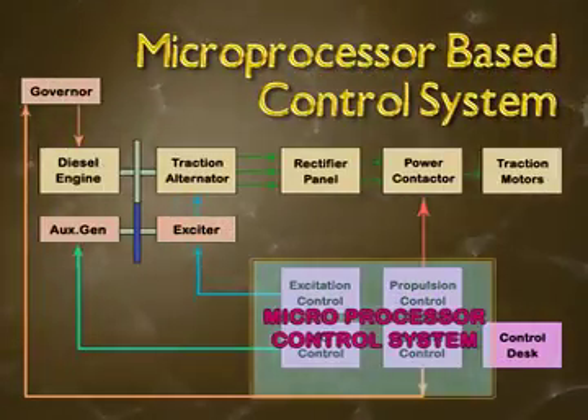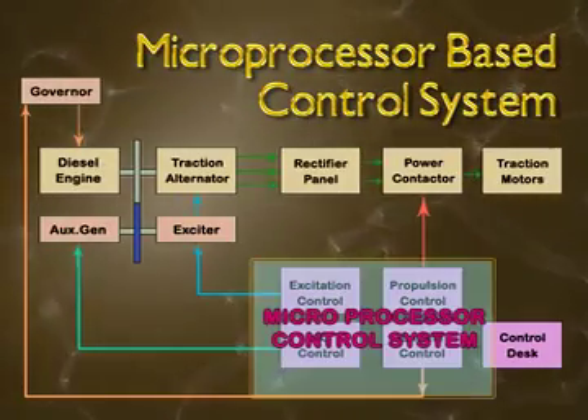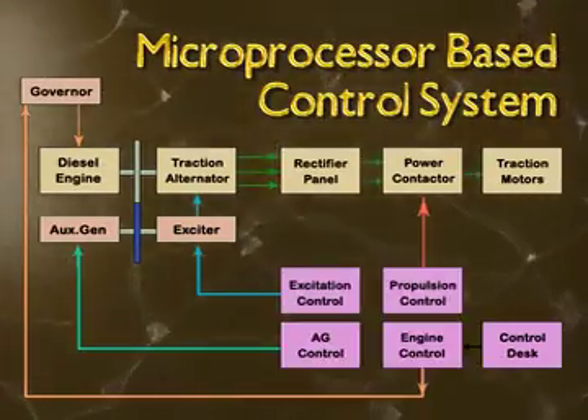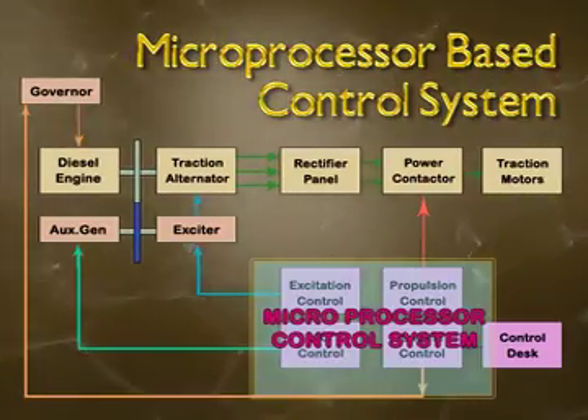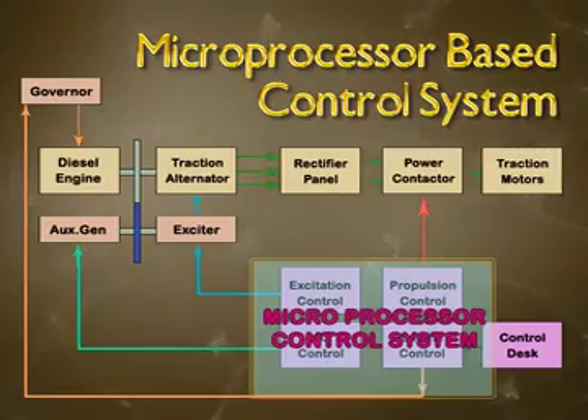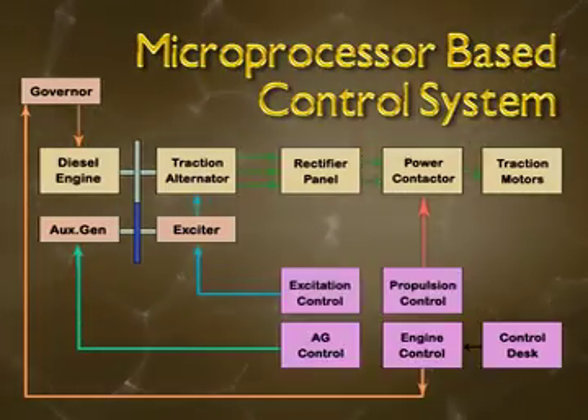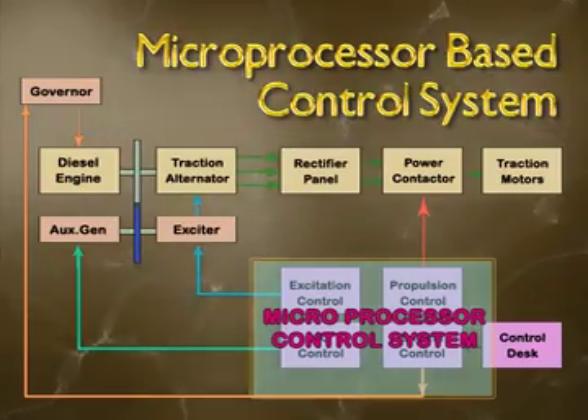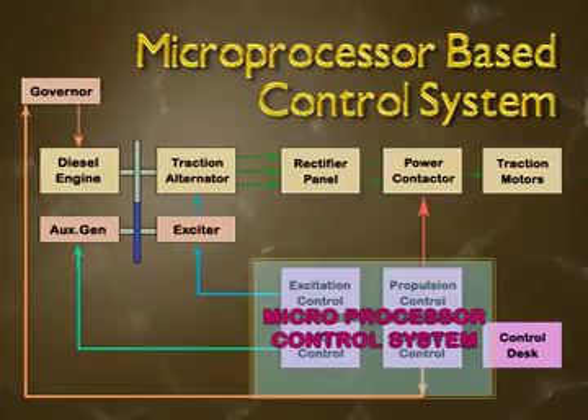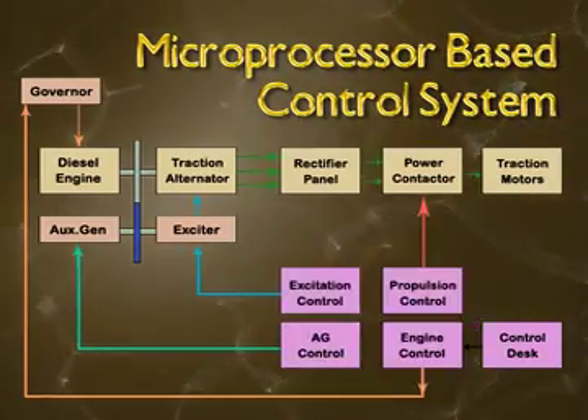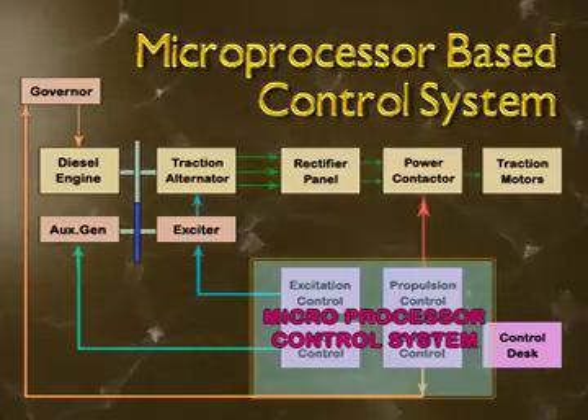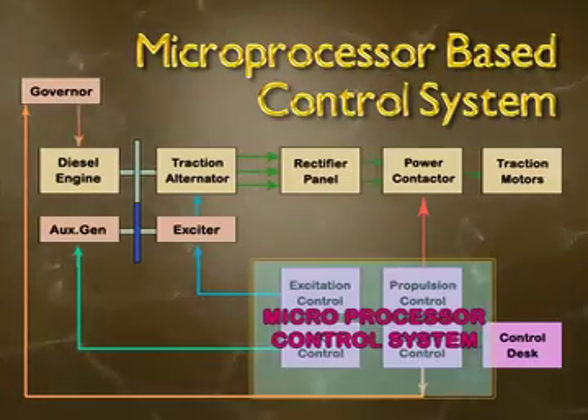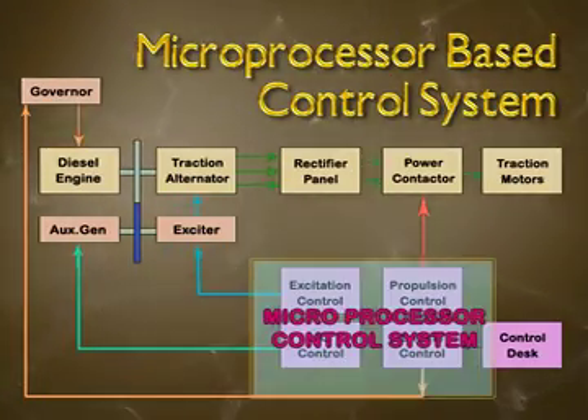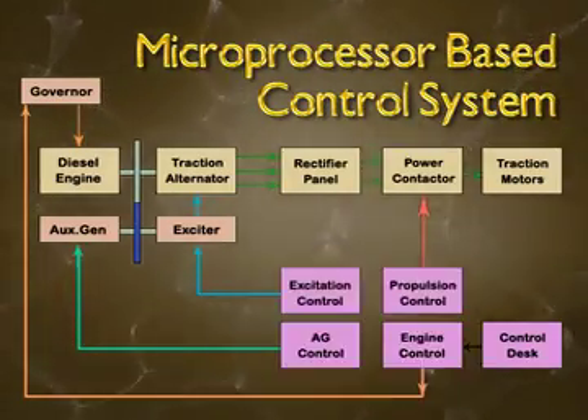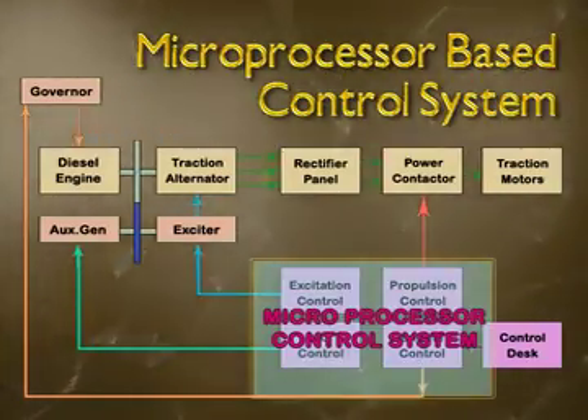The MEP 660 is a complete locomotive control system consisting of engine cranking, loco propulsion control, excitation control, auxiliary generator control, and continuous monitoring of safety devices on the locomotive. Some of the improved features are self-load test of locomotive and inbuilt event recorder designed and developed as per RDSO specifications. MEP 660 loco control system is designed to replace the existing propulsion and E-type excitation system. MEP 660 control system eliminates mechanical interlocking and uses a microprocessor to control the locomotive through software logic.